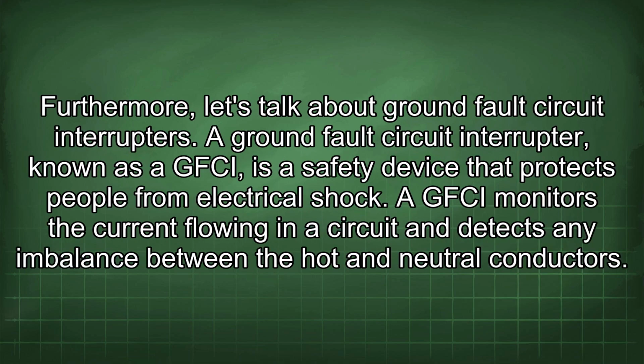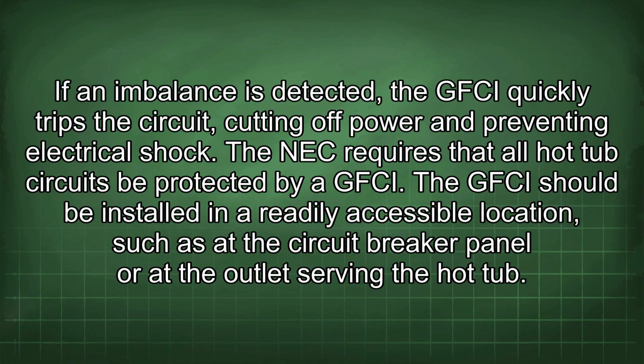Furthermore, let's talk about ground fault circuit interrupters. A ground fault circuit interrupter, known as a GFCI, is a safety device that protects people from electrical shock. A GFCI monitors the current flowing in a circuit and detects any imbalance between the hot and neutral conductors. If an imbalance is detected, the GFCI quickly trips the circuit, cutting off power and preventing electrical shock. The NEC requires that all hot tub circuits be protected by a GFCI.